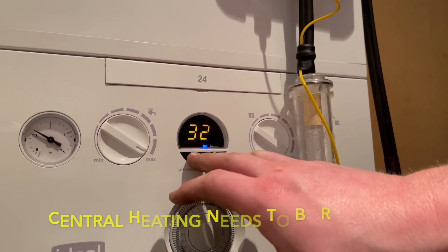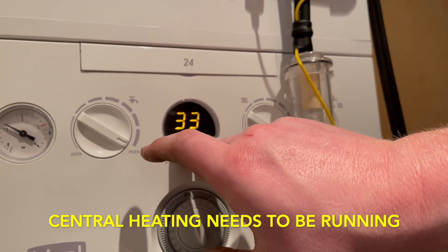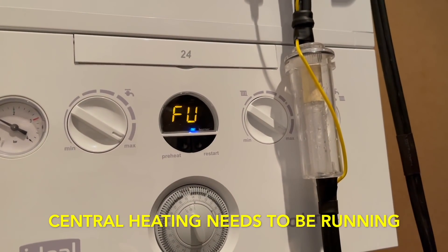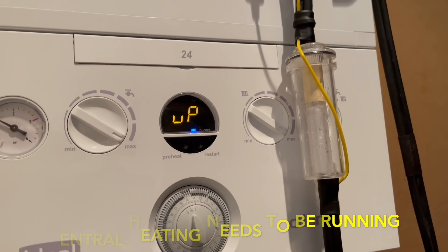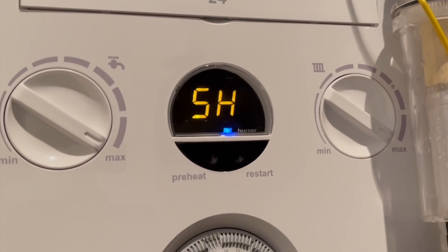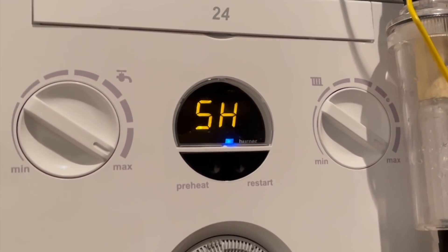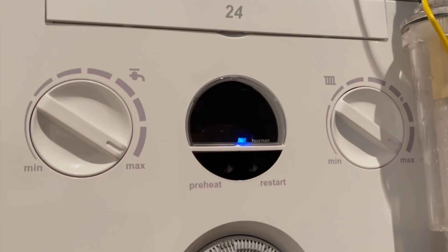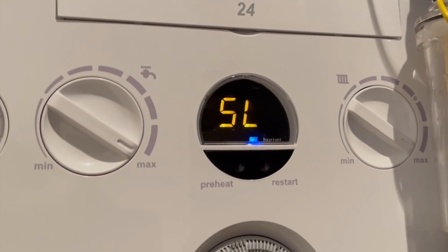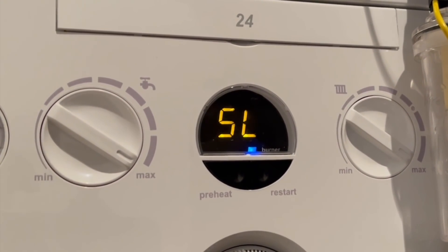To put this boiler into high fire, press and hold the pre-heat and restart button, and it comes up with a symbol meaning high rate. The boiler is now in high rate. To put it in low rate, press the pre-heat button and it goes into SL, which is your low rate. And it's as simple as that.